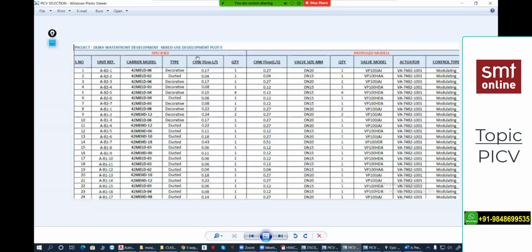Sir, I have a question. In the first FCU, we have a chilled water flow rate of 0.17, and then a chilled water flow rate of 0.27. So 0.27 is proposed. Available from the manufacturer, and 0.17 is the requirement. So that's the reason we are setting it to 62%, because they are offering more than the requirement. So 62% means balancing. We'll do the balancing. If you're getting the exact flow, then no need to go for 100%. Suppose the manufacturer is also offering 0.17 and the requirement is 0.17, we'll make it 100%.